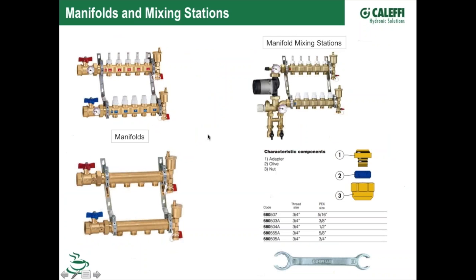Manifolds by themselves. This is probably the most common for PEX loops out to a radiant system. We can adjust the flow rate here. We can put actuators on it. We've got air removal here. We've got connections to fill and purge if you want to do it at the valve, isolation, temperature gauges.